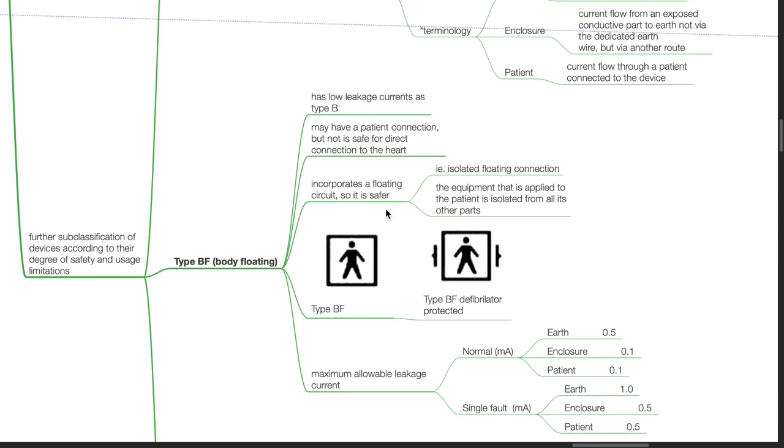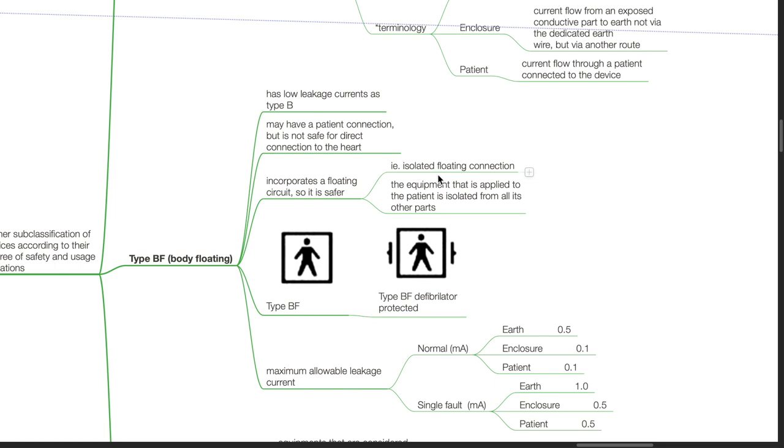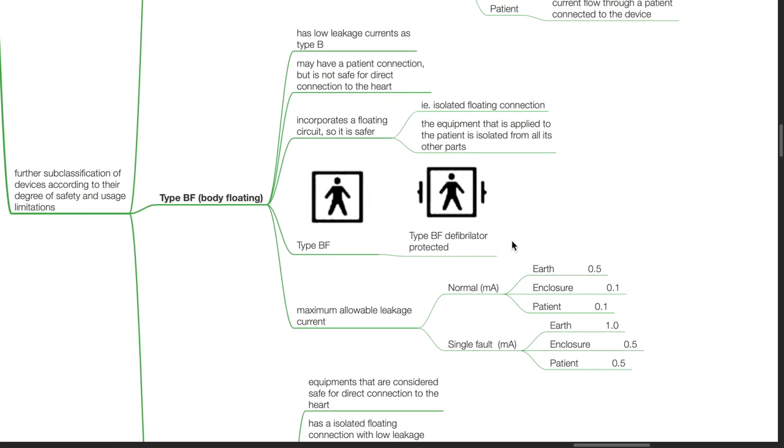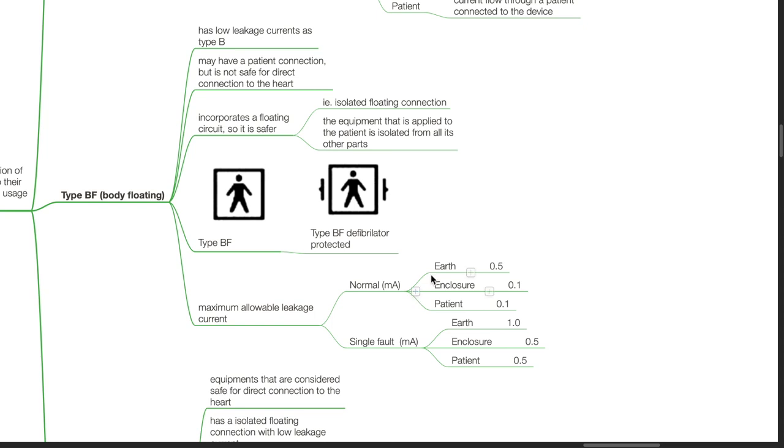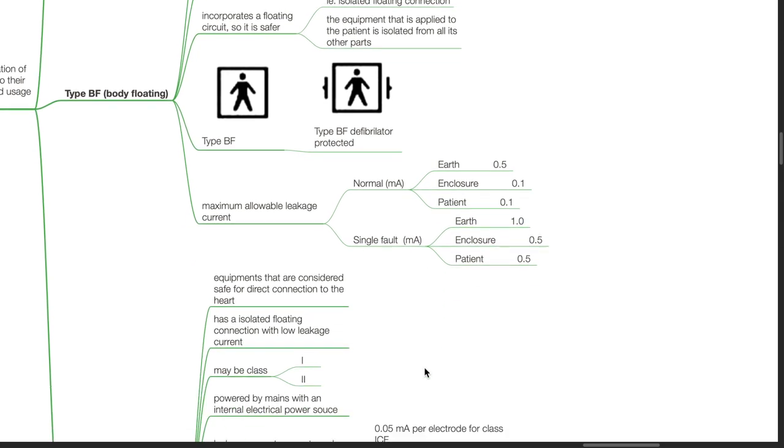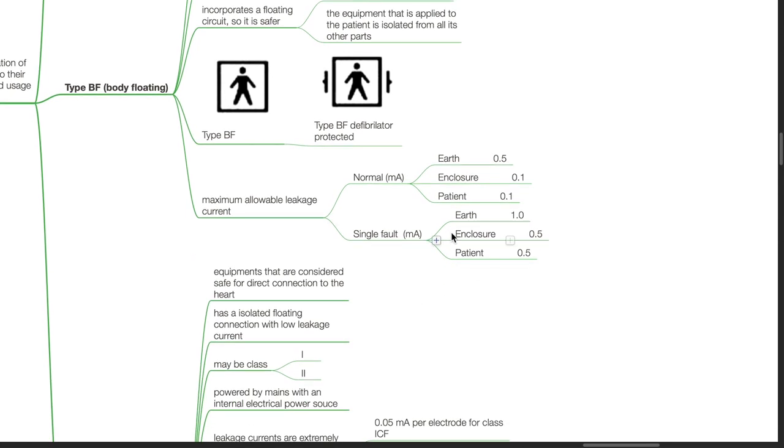Type BF or body floating equipment have low leakage currents as type B and may have a patient connection but are not safe for direct connection to the heart. These equipments incorporate a floating circuit, so they are safer, also known as isolated floating connection. The equipment applied to the patient is isolated from all its other parts. Maximum allowable leakage current under normal conditions: Earth 0.5, enclosure 0.1, patient 0.1 milliamps. During a single fault: Earth 1, enclosure 0.5, patient 0.5 milliamps.